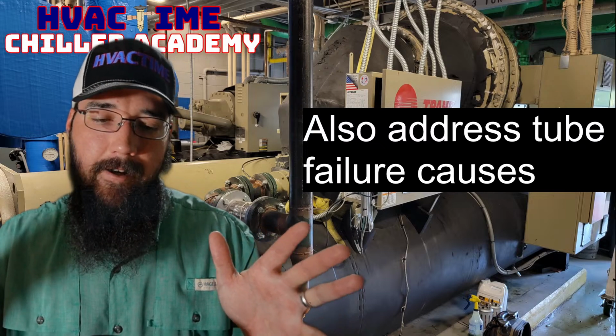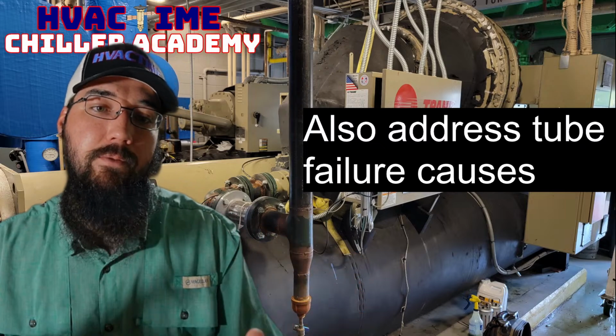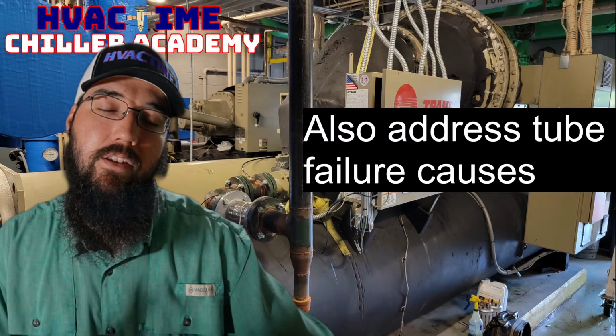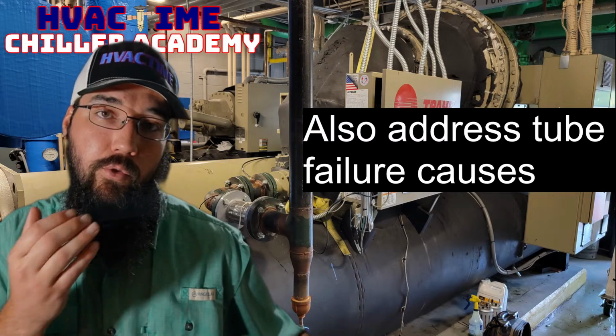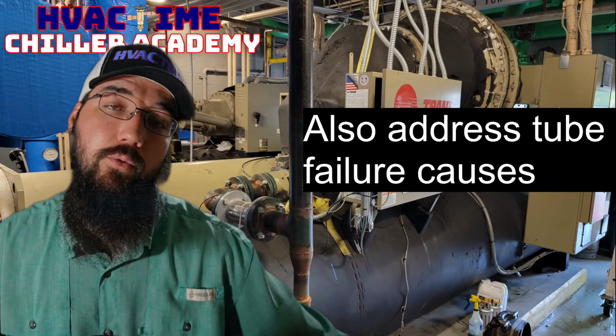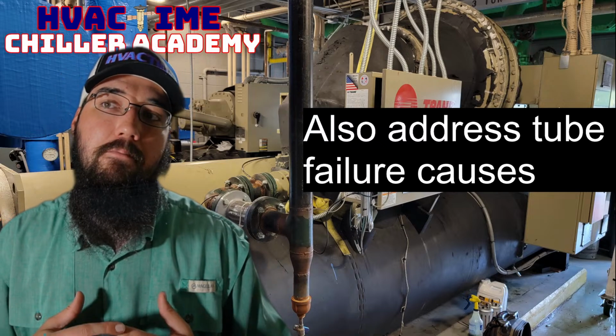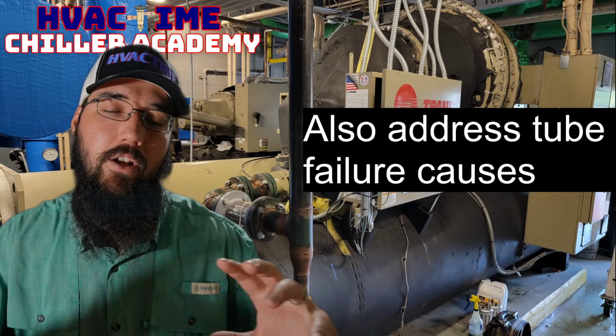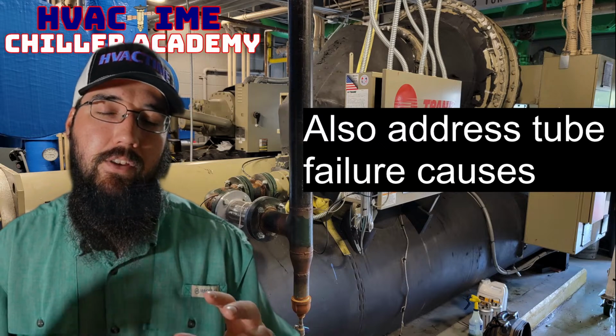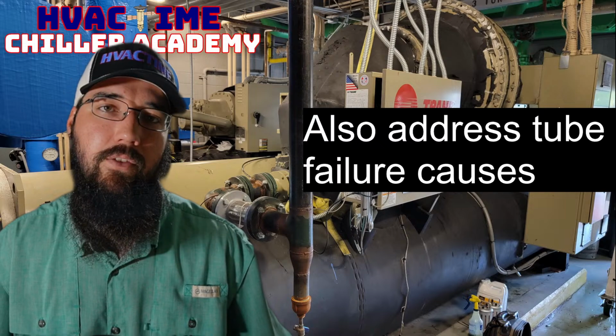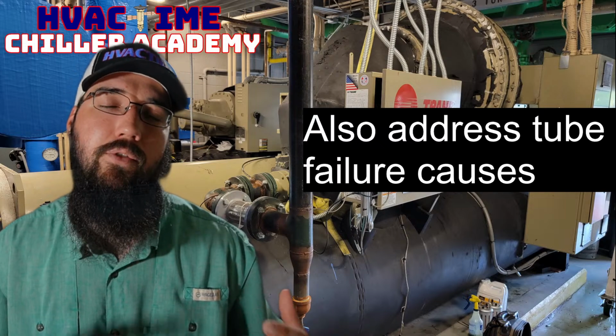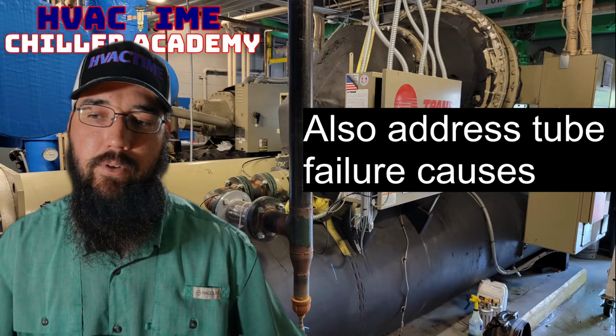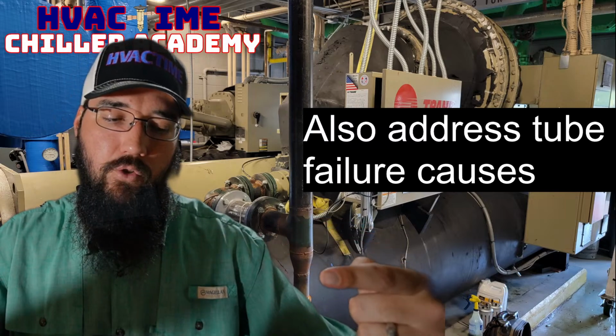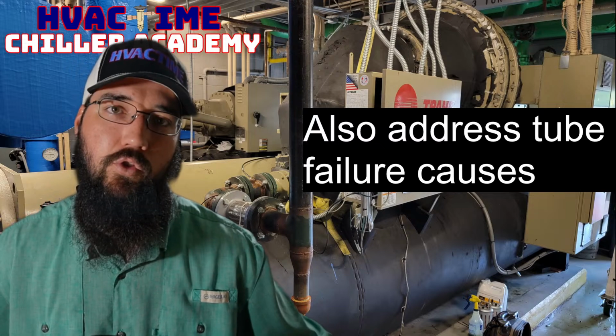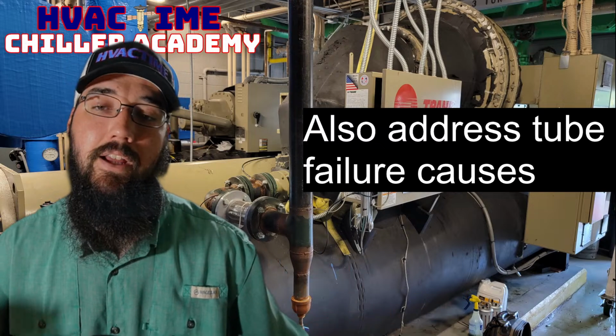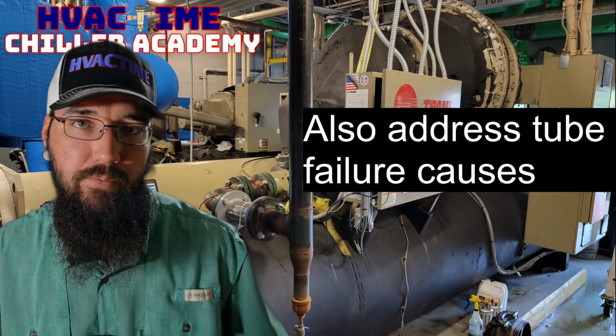In the process of trying to rebuild this machine and put it back together, it's going to be recommended to do a retube. And if you're going to do a retube, you're going to redo all the tubes - that is my recommendation. You're not just going to do the ones you think are bad, because the cost of going to that extent to begin with to bring that machine back to life is not worth the risk of leaving old tubes in place. You end up going through and just doing all the tubes new so that everything is fresh, and that's a very extensive process.